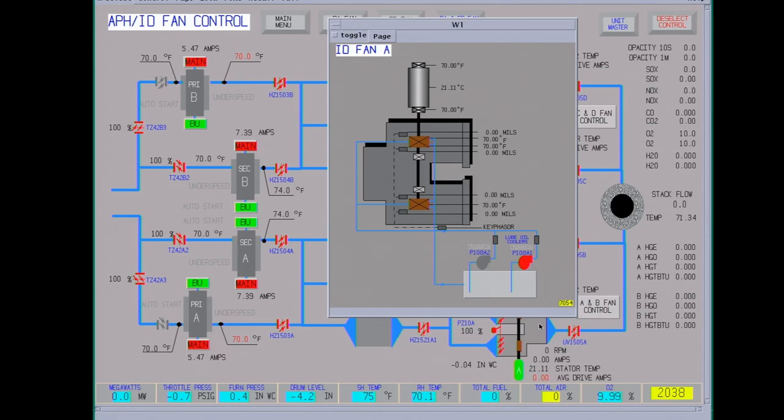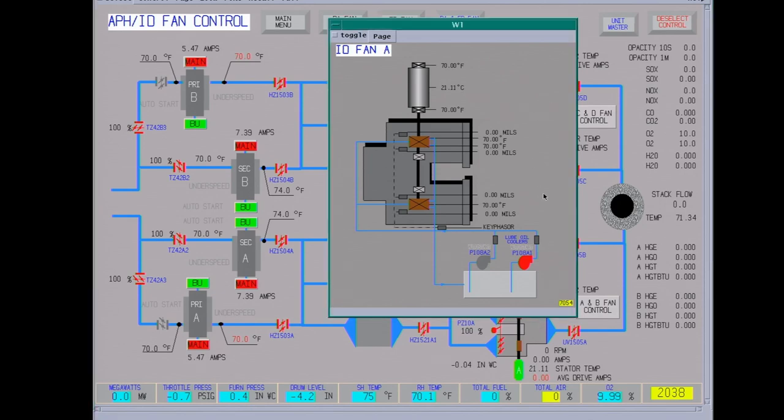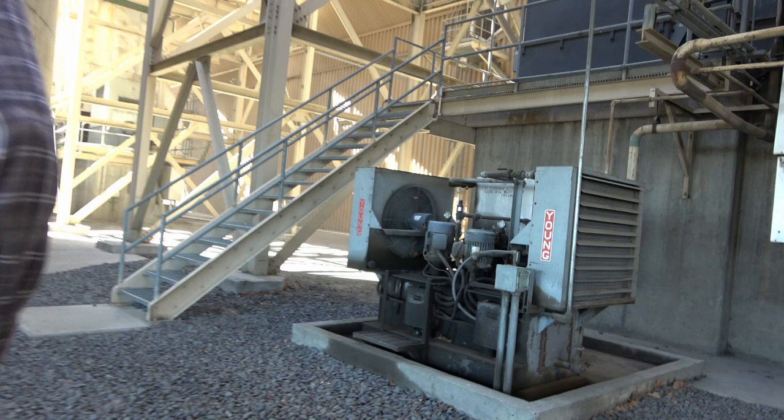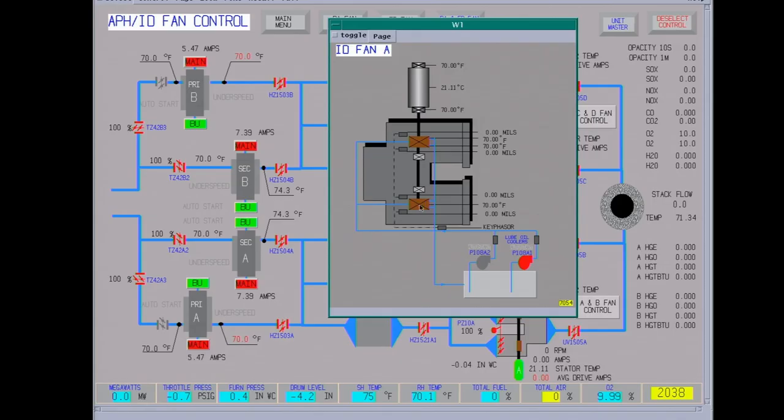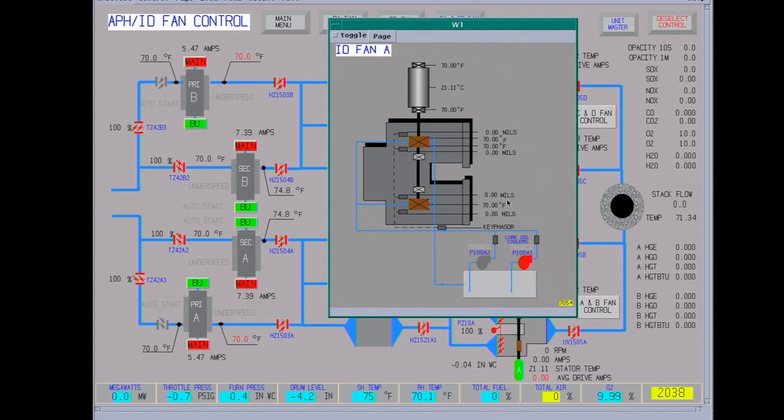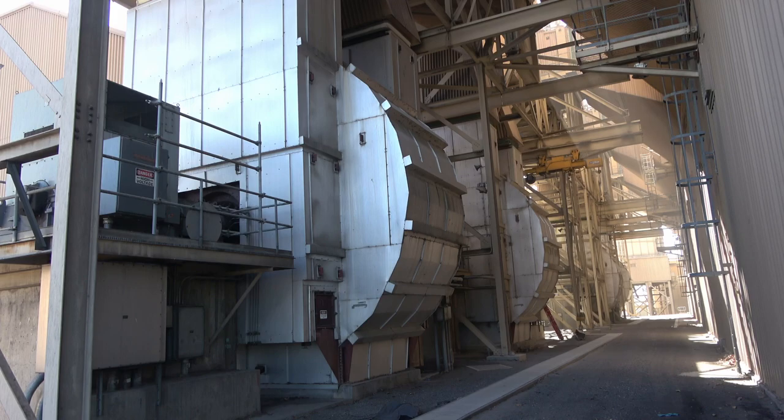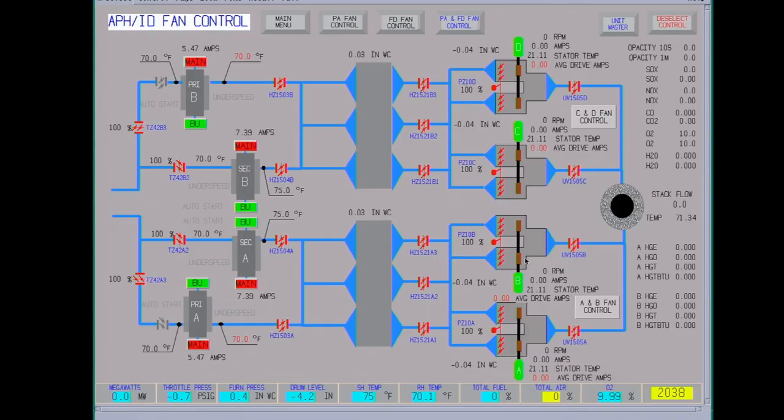Okay, this is the ID fan. There's a lube oil skid. The oil is cooled and strained and feeds the bearings. These bearings have slinger rings in them, so the oil is mostly for bearing cooling. It's a double suction fan, has vibration on it and temperatures. Like I say, the motors are 3,500 horsepower motors, variable frequency drive, so the draft is controlled by the speed of the motors.